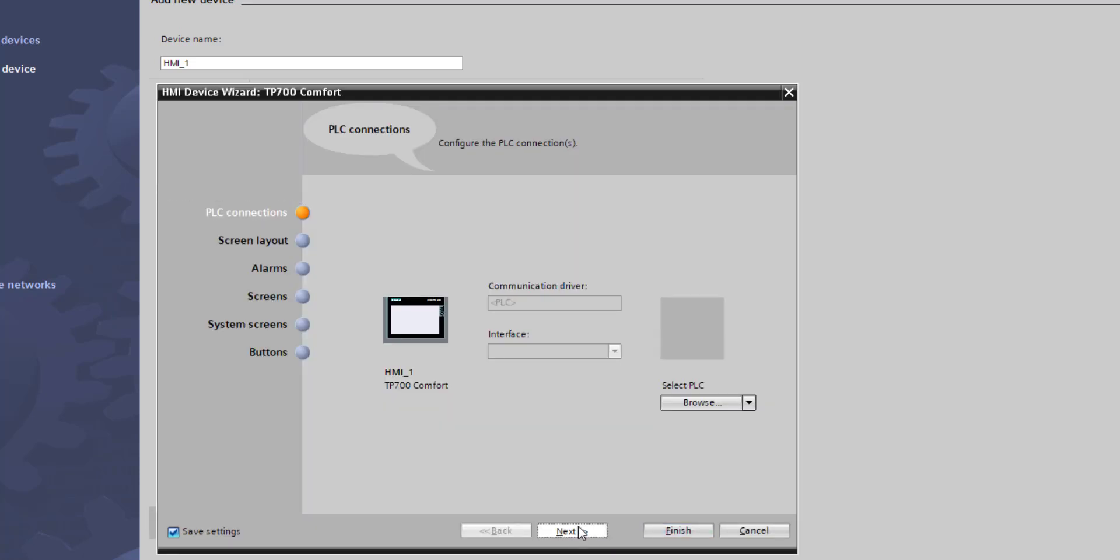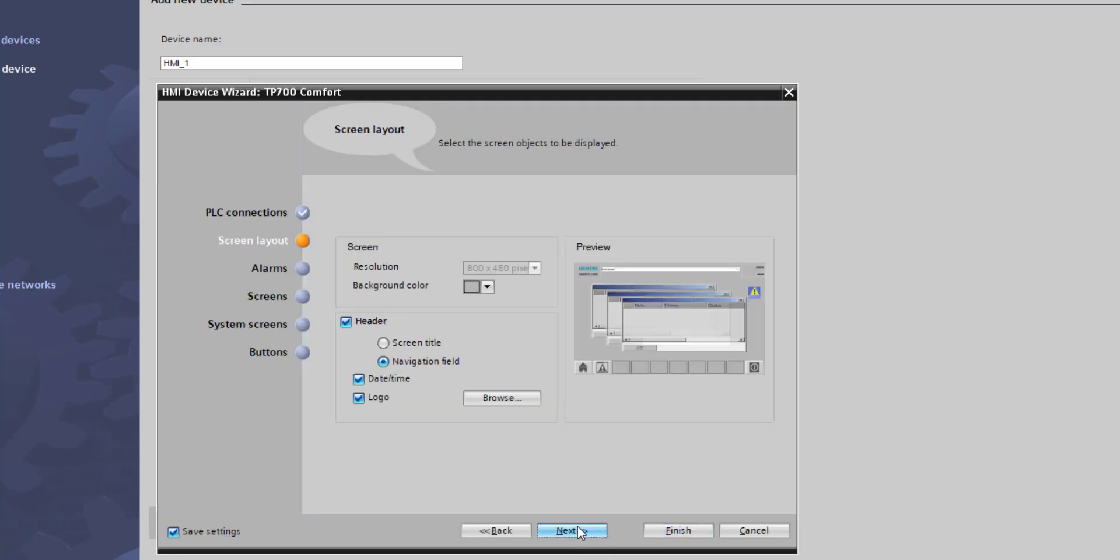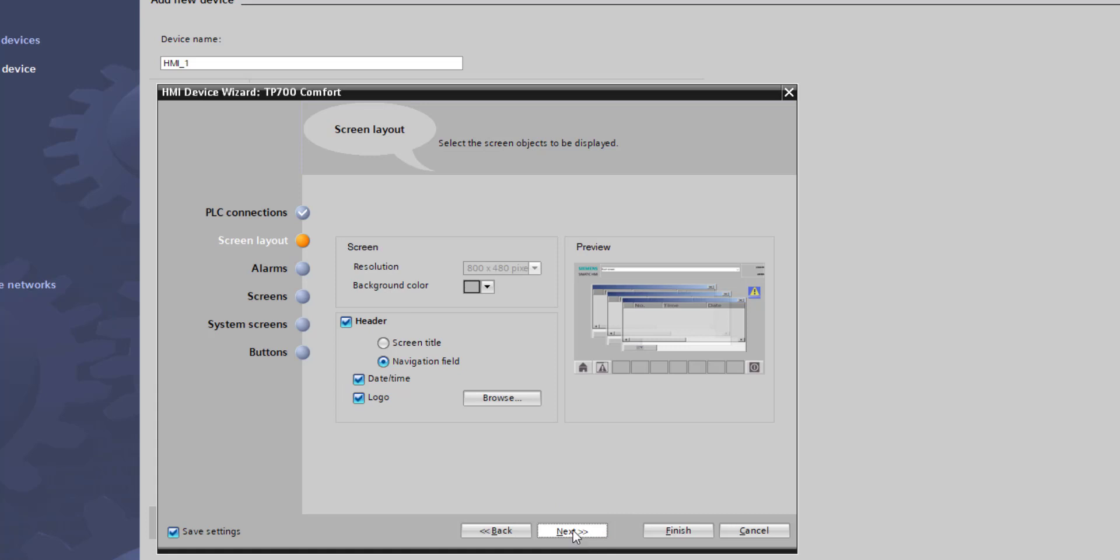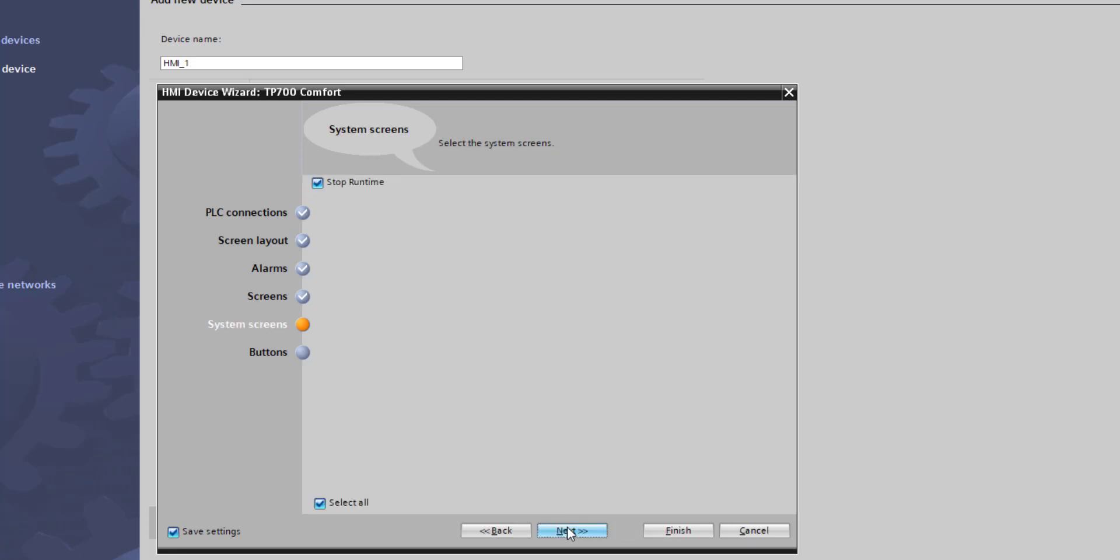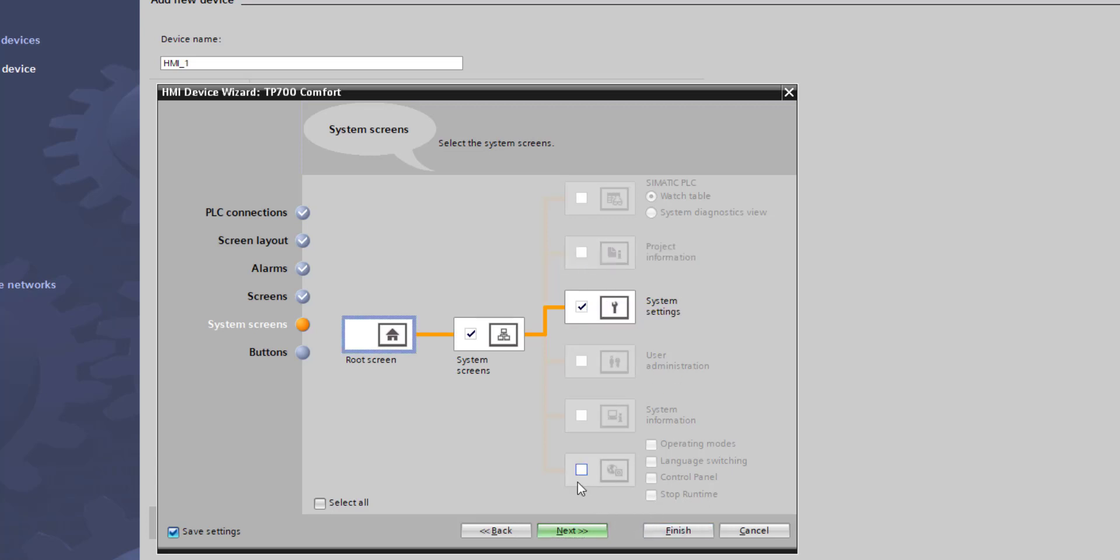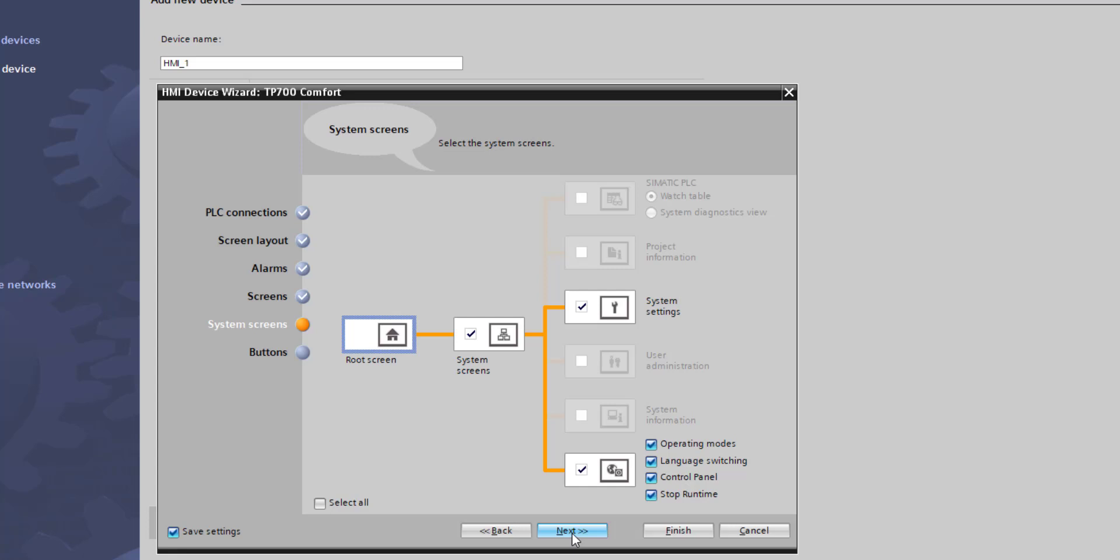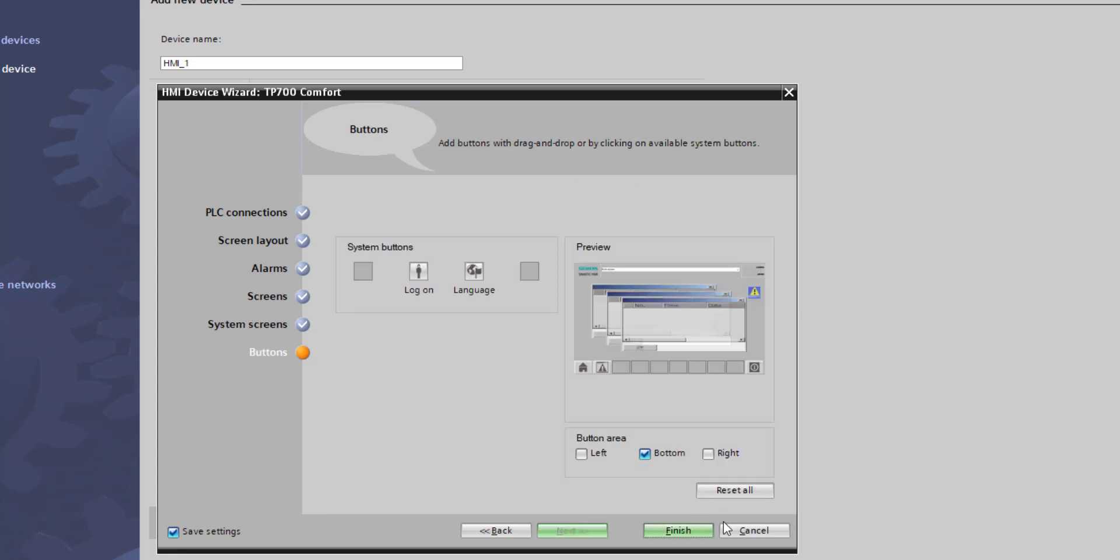This will take you through a wizard to set up some basic screens. As you can see, it's going to put the date and time, and I've got the option for a company logo. I want an alarm window. I want a root screen - this is setting your home screen so the one that the HMI powers up on. I've ticked that from my root screen I want to be able to get to system screens and system settings. You can select other options here. Stop Runtime is always a good option because it takes you back to the Windows CE desktop. Where do I want my buttons? On the bottom, and then I'm going to finish.